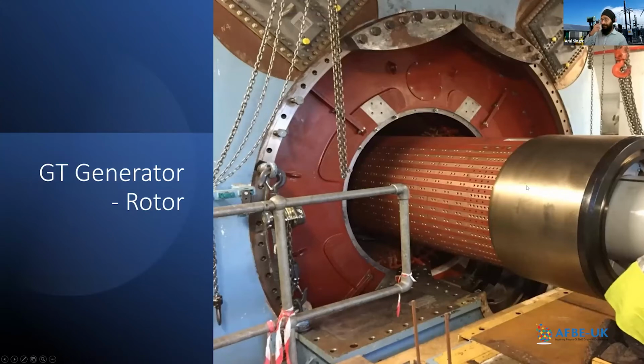This is the rotor. In simple terms, it's a coil spinning around a magnet - this being the coil, this being the magnet. The coil itself, called the rotor, was extracted during a forced outage in 2017. This rotor weighs 46 tons and spins at 3000 RPM. It's a two-pole rotor, and our generators are enclosed with hydrogen for cooling purposes.